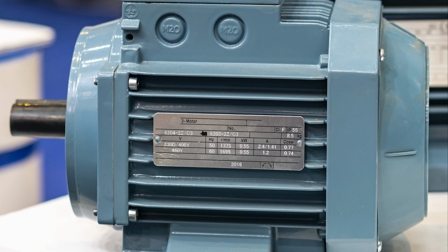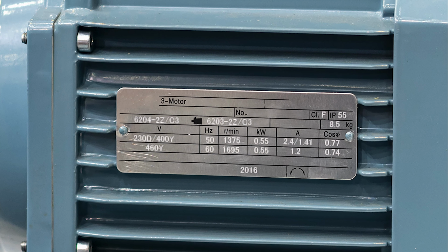This means that the frequency of the alternating current dictates how quickly the rotor turns. The more times the three phases are repeated around the stator, however, the slower the rotational speed. More poles do, however, result in a greater force or torque from the motor. Motors like this are therefore always described in terms of their number of poles, along with their number of rotations per minute, or RPM, for a given frequency of electrical supply, as well as their power output.